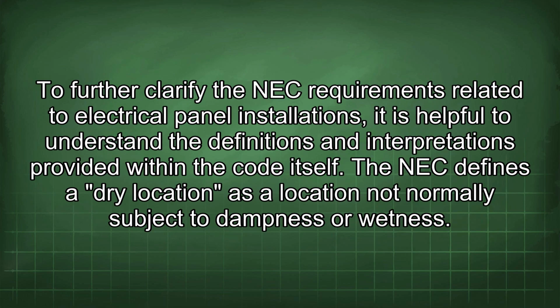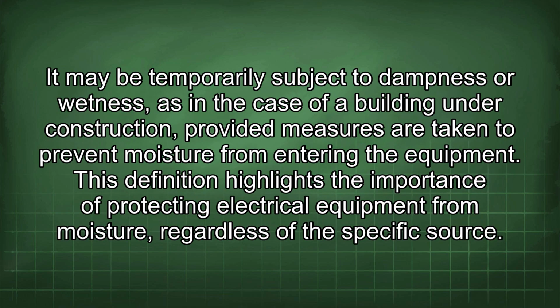To further clarify the NEC requirements related to electrical panel installations, it is helpful to understand the definitions and interpretations provided within the code itself. The NEC defines a dry location as a location not normally subject to dampness or wetness. It may be temporarily subject to dampness or wetness, as in the case of a building under construction, provided measures are taken to prevent moisture from entering the equipment. This definition highlights the importance of protecting electrical equipment from moisture, regardless of the specific source.